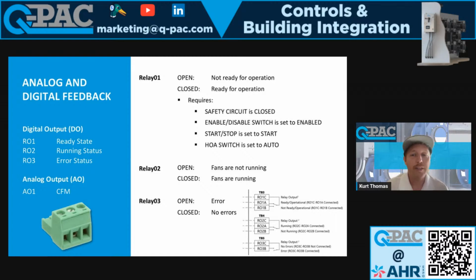All right, analog and digital feedback. So if you want more feedback than just what you can get via BACnet, then you can use these digital and analog outputs. So if you want to monitor airflow, then we do have an analog output. It outputs a 0 to 10 volt signal. But depending on the actual system you order, you can look in our HMI and it'll tell you what the high end is. So the low end's obviously 0 CFM. The high end will tell you in the HMI, and then it's just a linear progression up there.